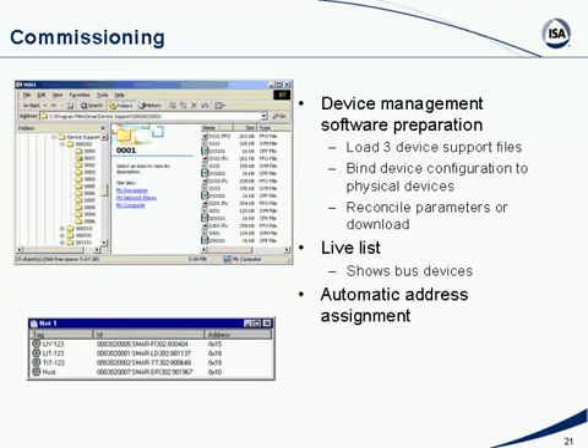Commissioning Fieldbus devices is actually quite simple, and this is one point where you can have considerable CapEx savings with Fieldbus. Not only the wiring reduction, but the fact that commissioning devices can actually be a lot faster. If you buy your Fieldbus devices with a tag pre-assigned by the factory, when this device is hooked up onto the Fieldbus, it gets automatically detected by the system, and basically it commissions itself. So you can commission a device maybe in 20 minutes or less with one person, as compared to two people working an hour or two, as would be the case with 4 to 20 milliamp, when you need to radio each other with walkie-talkies, etc., to bring out the wires. Okay. So when I hook up the device, it's automatically identified and detected, obviously, and assigned an address. Okay, and it automatically becomes bound to the placeholder in the control system.